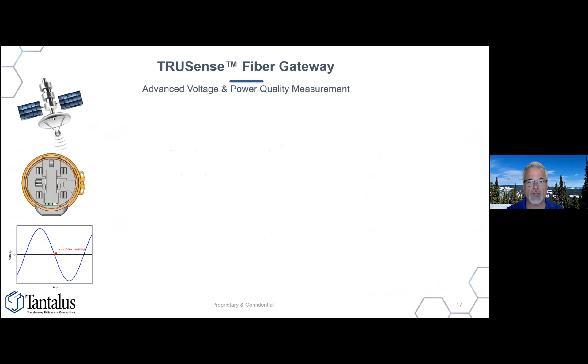So you will be able to select one or more measurement channels. So you have a full menu here. So we can sample voltage, amperage, volt amps, kilowatts, so demand, instantaneous demand. You can look at kilowatt hours. You can look at power factor and total harmonic distortion. And each of these are going to be sampled 256 times per cycle, or over 15,000 times per second, okay?